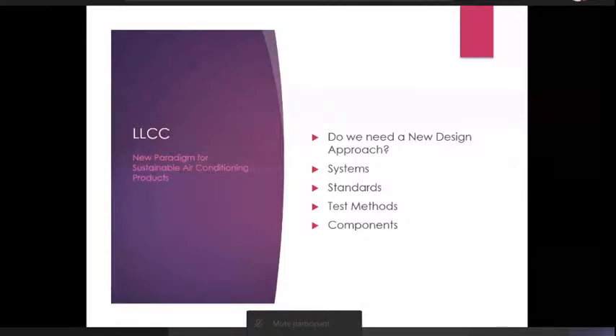We'll go ahead. So now, what is the new design approach, or do we need a new design approach? Now on that I'm clear that we need a new design approach, because as we saw, if we don't make changes to our approach, then we will cross the sustainability limit. So we need to look at a new design approach, and then what are the elements that will be forming a part of the new design approach. So we have discussed systems. We'll need to look at standards. So once we make new designs available, there's a new approach to looking at sustainable design. We need to be able to measure the impact, whether it is part load efficiency, varying load condition, and low ambient condition performances.